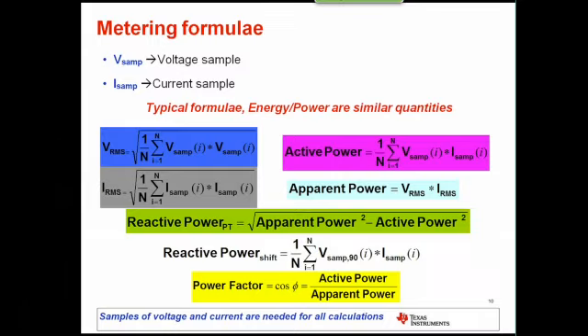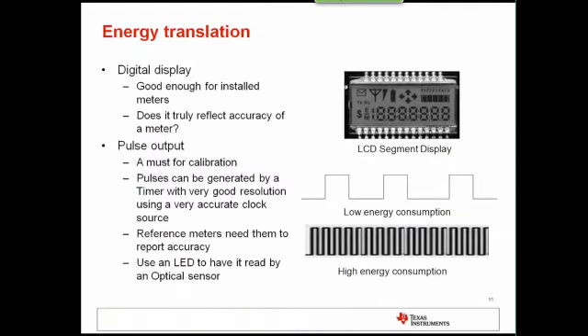And there are two ways to calculate the reactive power. First way is by taking the apparent power squared, subtracting the active power squared, then taking the square root of that. And the second way, which we actually use in our metrology algorithms, is to shift the voltage samples by 90 degrees, multiply by the current at that instant, accumulate over time, and then take the average. Power factor can be calculated two ways. One is by calculating the cosine of the angle between the voltage and current samples, and the other way is by doing active power divided by apparent power.